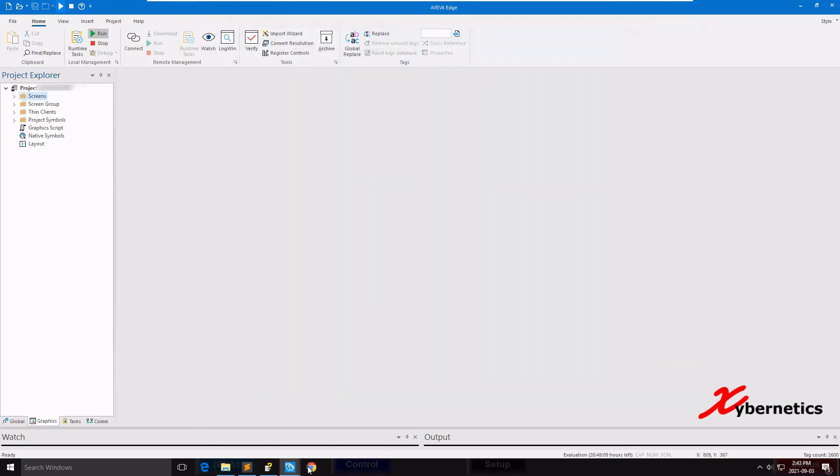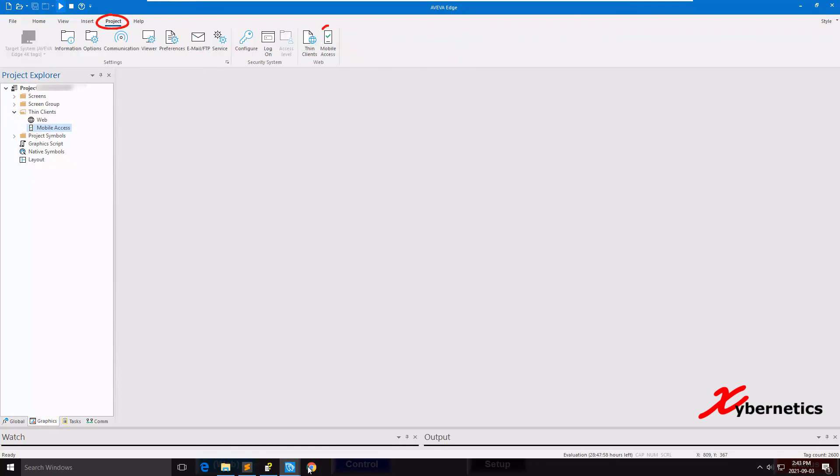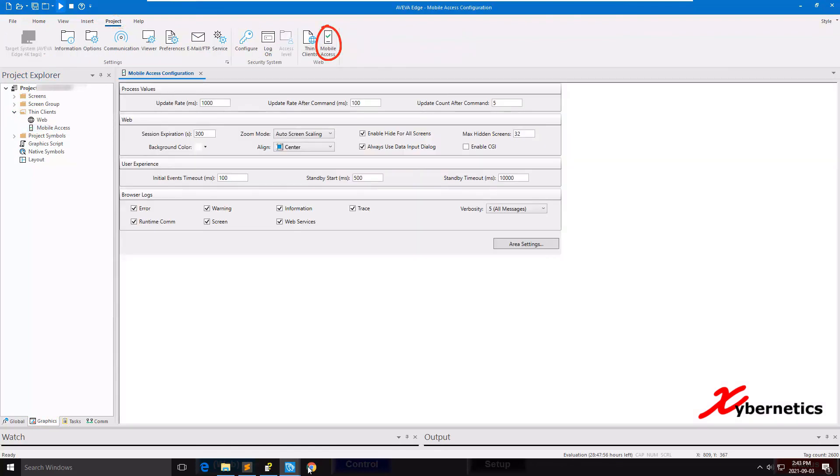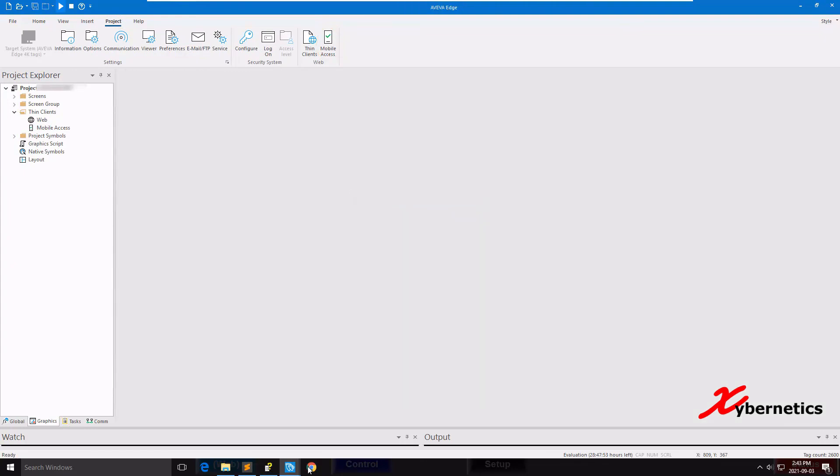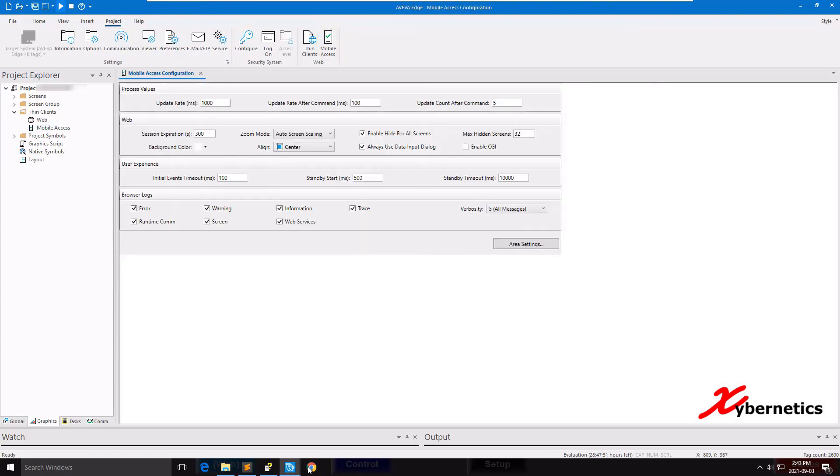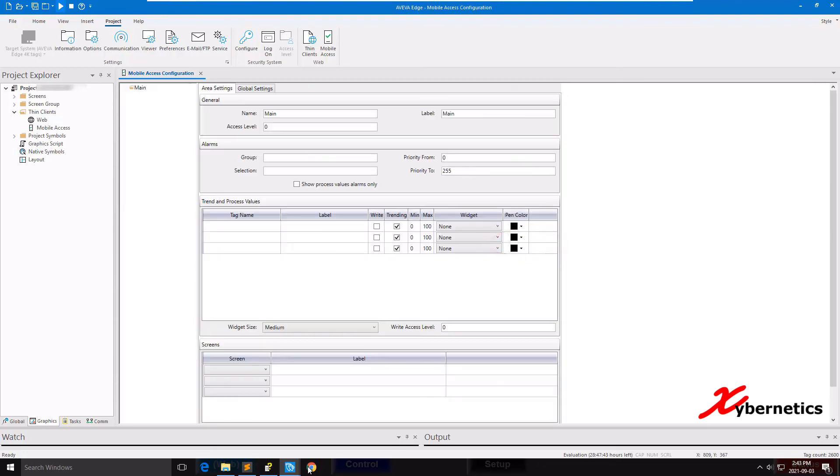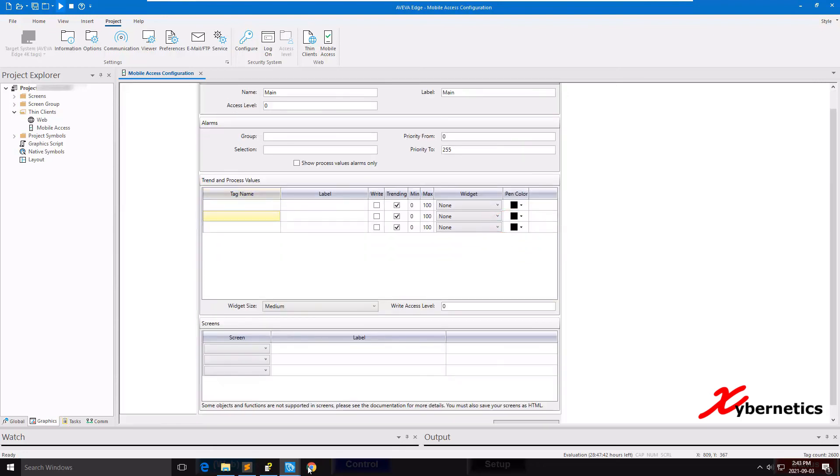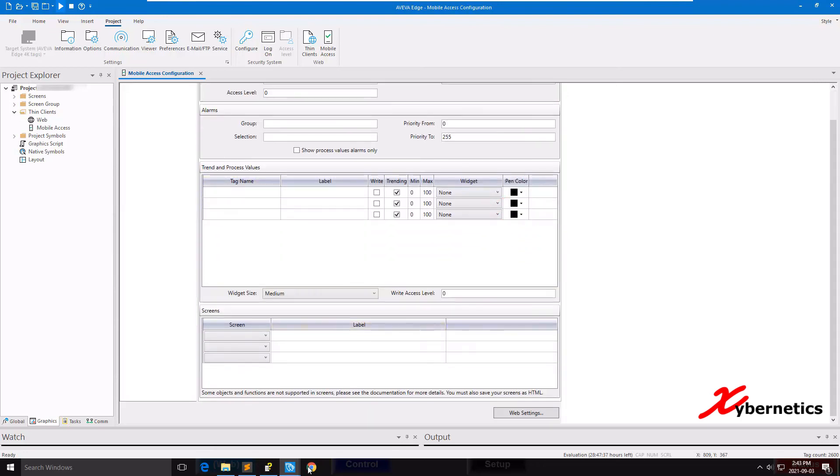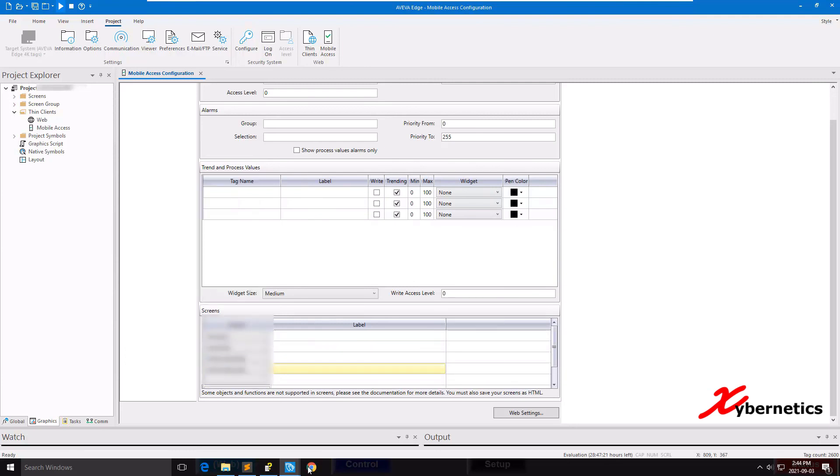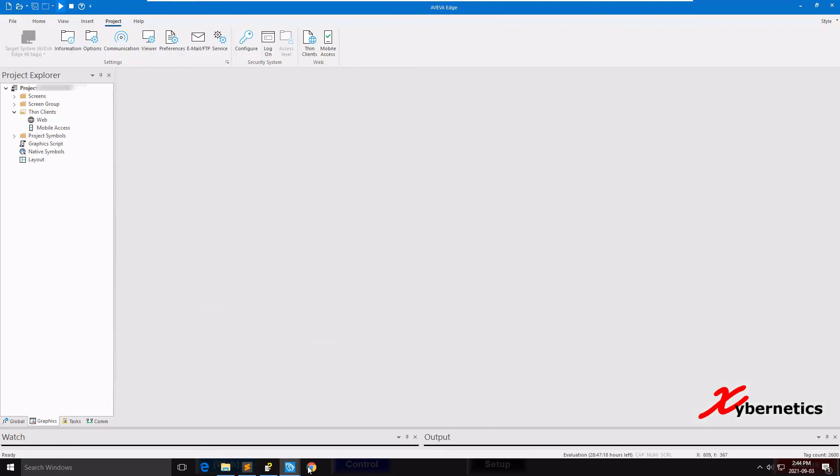To configure your mobile access, go to Graphics, Thin Client, and you have Mobile Access here. Another way to access this menu would be Projects, Mobile Access. They are the same thing. Over here you set your update rate. Everything else I normally leave as default. Go to Area Settings here. Over here you can define your tags and then the screens. You can define the screens here. I'm gonna choose a few screens. So I got four screens here that's ready to go. When you close it, it'll say Save.